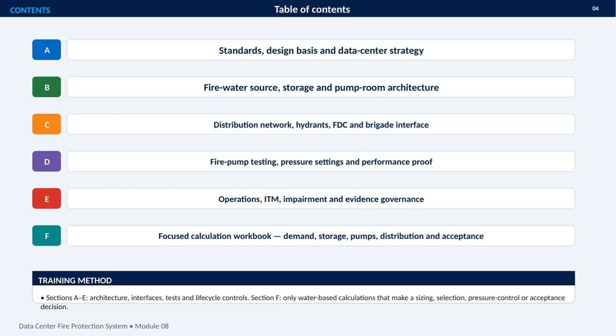This module is organized into 6 sections, moving from system strategy through design, testing, operations, and calculation. The overall goal is to connect the data center's fire protection architecture with the evidence needed to prove that it will perform when required. Section A establishes the standards, design basis, and broader data center strategy. Section B then focuses on the fire-water source, storage arrangements, and pump room architecture.